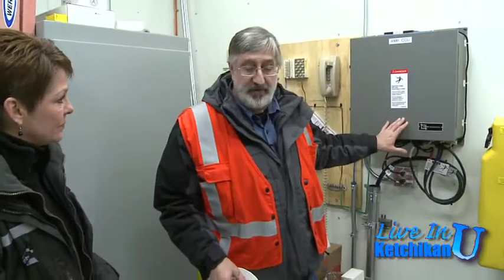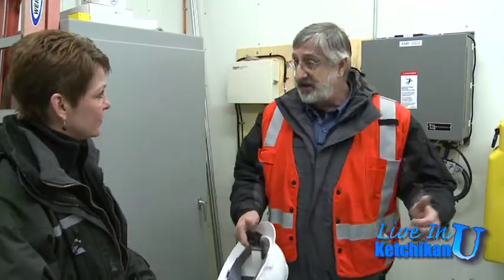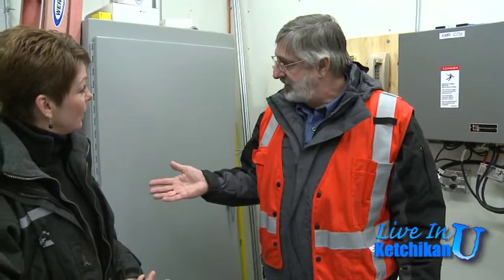Let me tell you about my house. It came with electric heat, multiple units and multiple thermostats. When I looked through the AMR software at my house, it's difficult to manage something you can't see. Right now that information isn't available for the average customer, you'd have to come down to our headquarters per meter. We don't have it on a wide network yet. But since I had that ability, I could look, and in one day I cut my usage in half just by looking at the thermostats, programming them down, in some cases turning them off completely. I also found two broken thermostats, one that was on constantly, and was able to fix that. So in one look, I could make that determination.